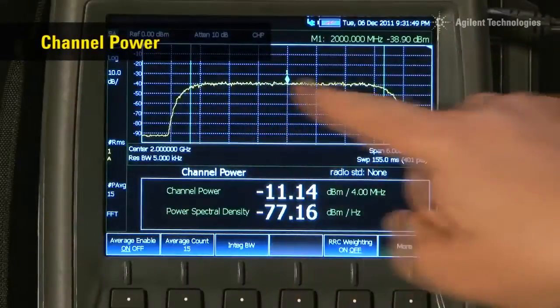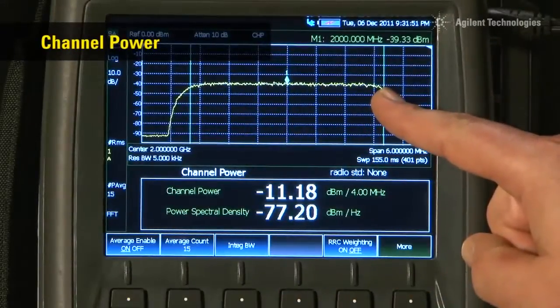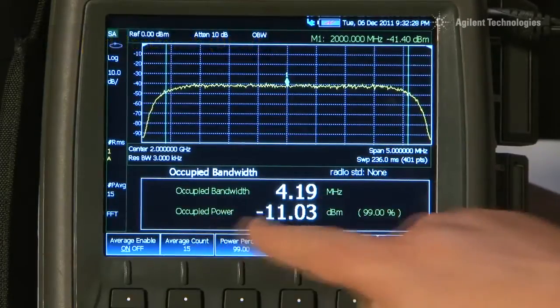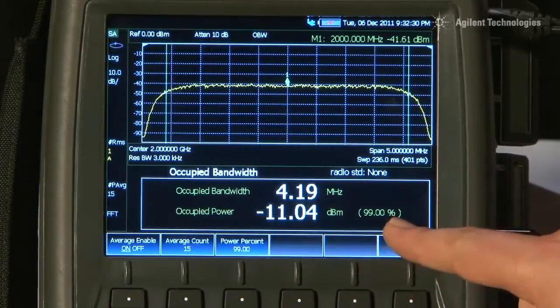The FieldFox will automatically measure channel power of modulated transmissions, such as this spread spectrum WCDMA signal. We can also measure the occupied bandwidth of the signal. Here you can see the occupied bandwidth is 4.2 MHz, and the power is minus 11 dBm.